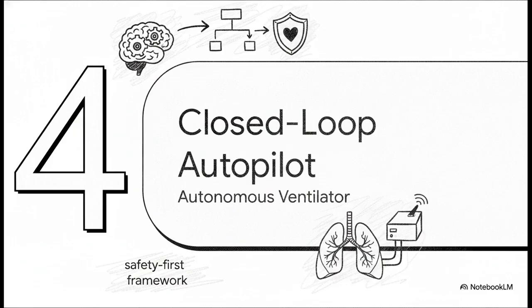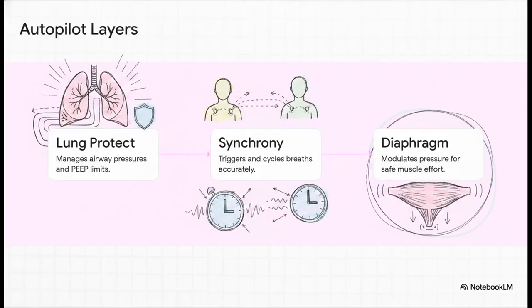This right here is the core proposal of the source paper, moving away from constant manual tweaks to a fully automated, safety-first theoretical framework. Let's break down how this builds into an actual working architecture. The proposed closed-loop system runs 3 parallel layers right inside the ventilator's microprocessor. First up, the lung protection controller continuously adjusts airway pressure and PEEP to keep those transpulmonary pressures safe.